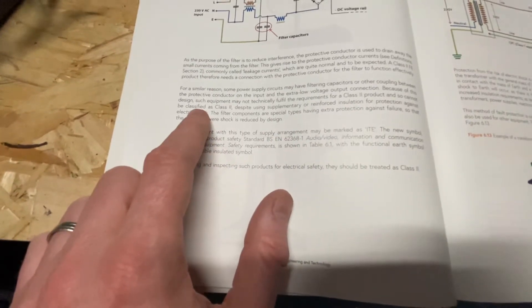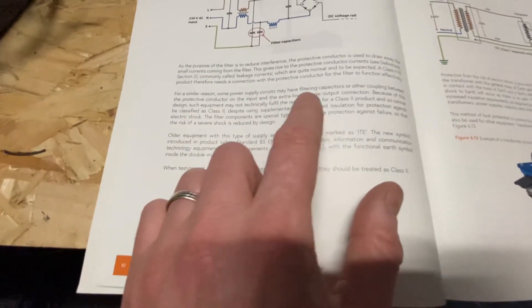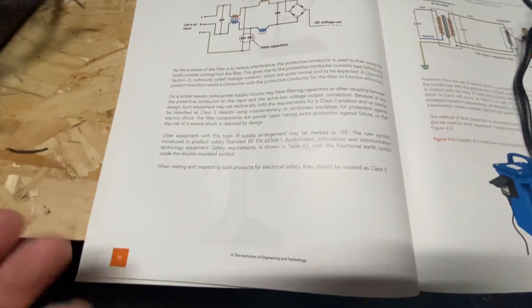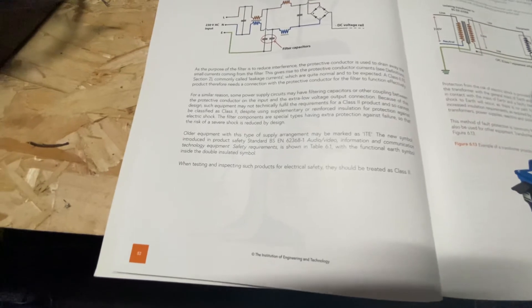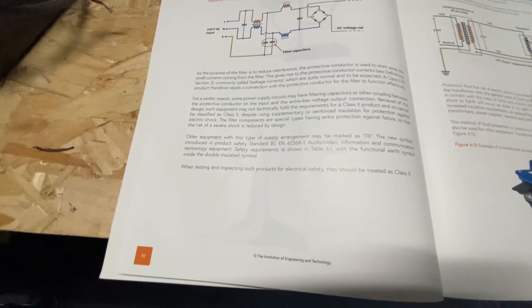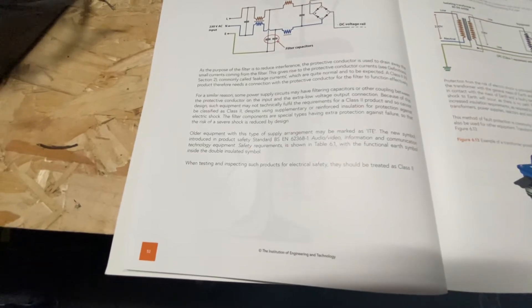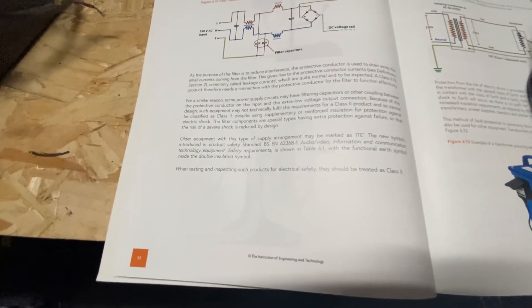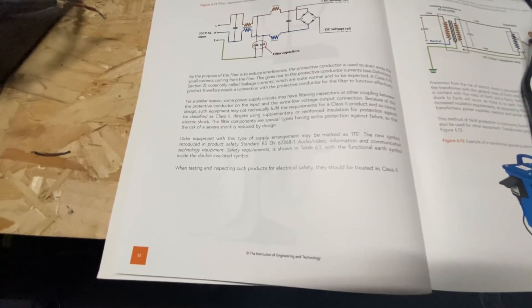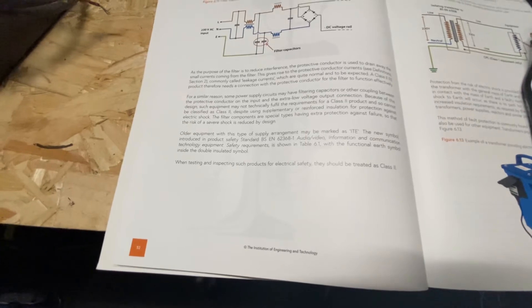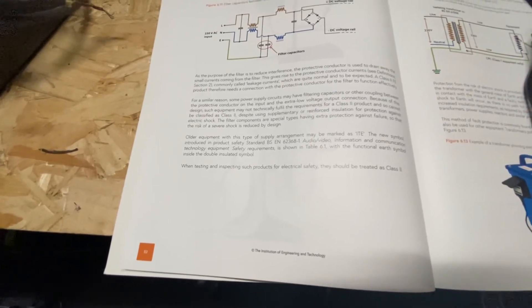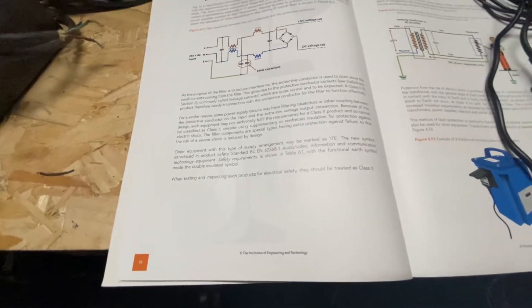It says here, because of this design and the design being that some of these supply circuits in the charger have capacitors and filters and things like that, such equipment may not technically fulfill the requirements of class 2, so cannot be classed as a class 2, despite having supplementary or reinforced insulation for protection against electric shock. So basically, these chargers have various components inside which give extra protection against failure, so the risk of severe shock is reduced by design.